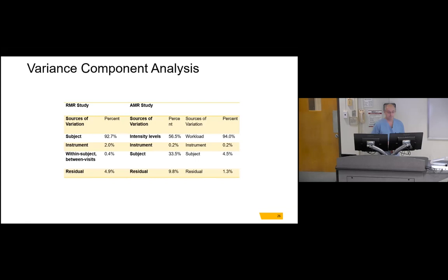And for the exercise study, that's definitely yes, because when you are measuring a range of the energy expenditure, the errors coming from the difference of the instrument are tiny. It's only 0.2%. So this gives us a very good signal that our instrument is not only very precise and accurate, but also gives us some hope that if we wanted to conduct multi-center studies, we can with these different types of instrument, provided they are well calibrated and maintained. Okay, that's all for me.